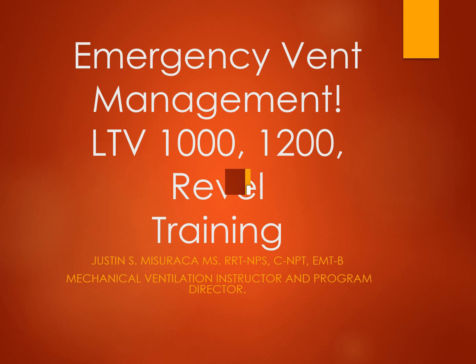Alrighty, rise time. This is one of the ones that gets us in trouble if we're not paying attention to what we're doing. Rise time, you have to press your select button and hold it down for 3 seconds. That'll allow you to get into the back modes and turn the dial over till you get to rise time, and you'll see a 1 to 9 variable on there. 1 being the fastest flow, and then 9 being the slowest flow. So let's talk about that real quick.